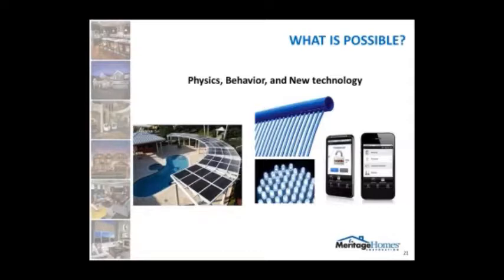Okay, and then one last comment about the dehumidification, which is, is it better and cost-effective to use a dehumidifier instead of a higher tonnage AC? No. A dehumidifier is an energy pig. It is very, very energy intensive to dehumidify through a dehumidifier, where you get the in-parallel benefits of dehumidification through AC. The challenge there is the AC is not running in the spring and the fall, where the humidity still exists. And so the AC doesn't handle shoulder months where a dehumidifier would.